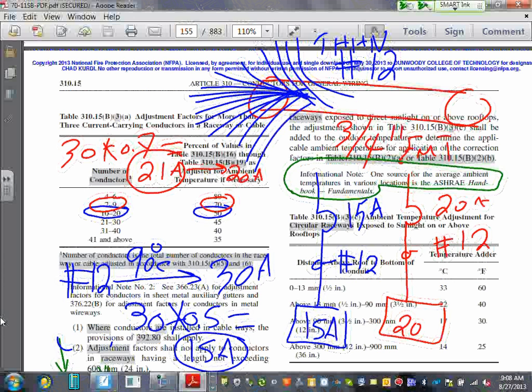When I do this one, guys, I cannot emphasize enough: when you deal with conductors, and I don't know how the teachers explained it to you, but when I teach master and journeymen, when they sit for the master exam, that's how the state will test you. They emphasize the normal operating condition of the circuit. That's the first thing you want to start with. What is the normal operating condition of the circuit? Then you derate. Your derating here must be less than this, or this is the normal operating condition. If I end up here with 21 amps, can I pull 21 amps out of this circuit? No. Why? Because the normal operating condition by the code is this, based on the small conductor size and the 60 degree column. Any comments, guys? Any questions?